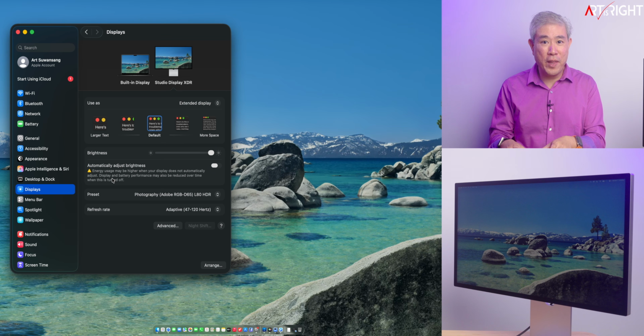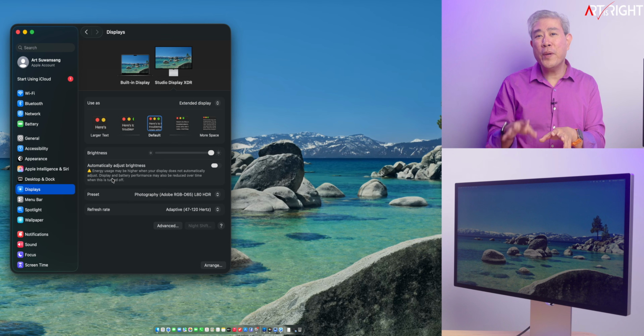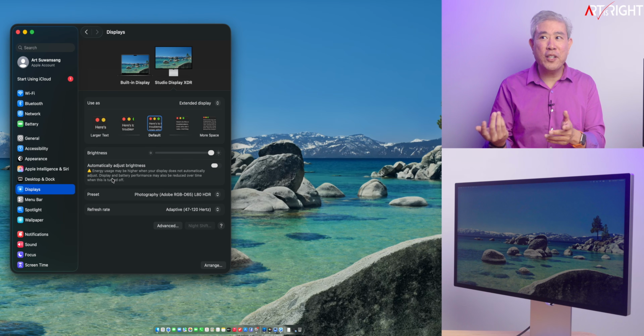So if you have a 14 or 16 inch MacBook Pro, for example, M1, M2 generation, and you're using it a lot, you might create a custom preset mode, set the display luminance to, say, 100 nit, and your display is only showing 90. This is where you want to do the full calibration so it adjusts the baseline again, so you're not out of range and your display shows more precise luminance.